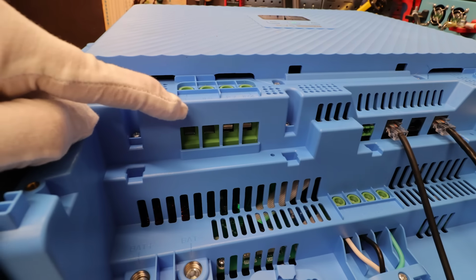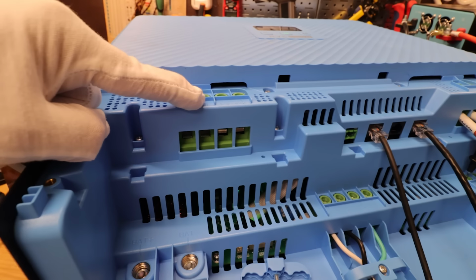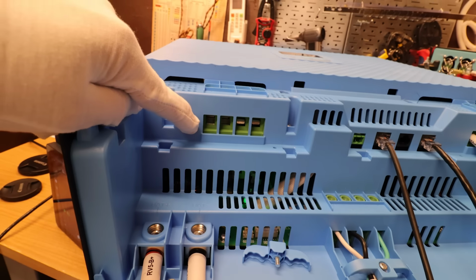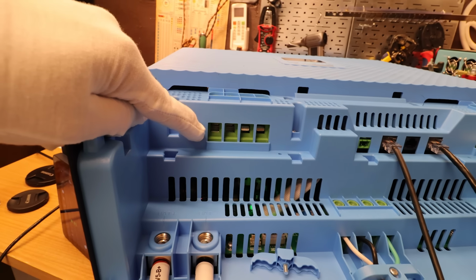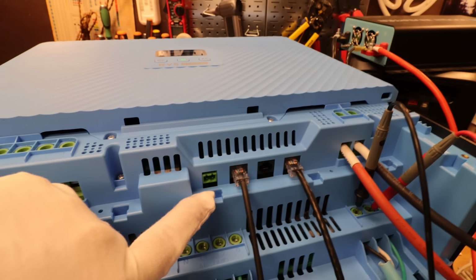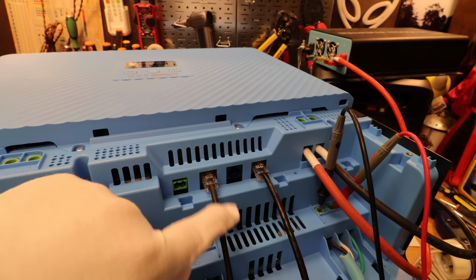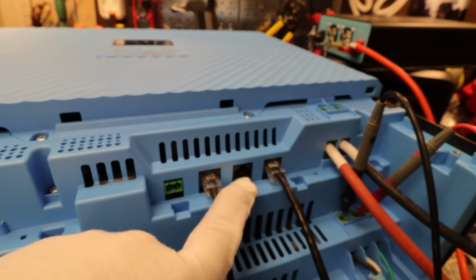Okay, so these are your two PV inputs — PV1 and PV2. You have to put raw crimped cables into this; you cannot use any kind of connectors. Here's your temperature sensor, your battery pack communications cable, and this is the EMS port, whatever that does.